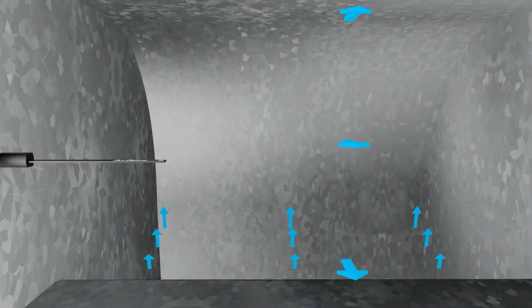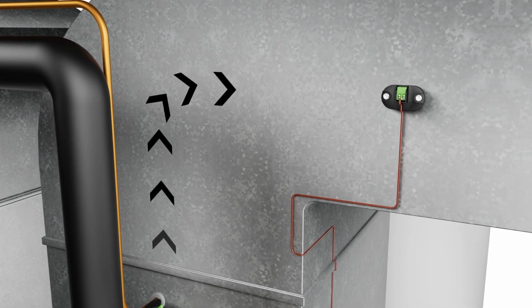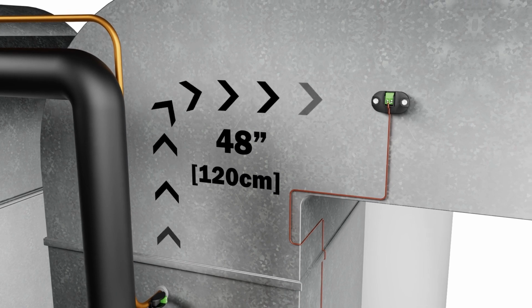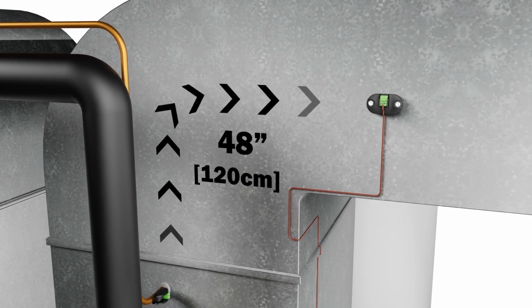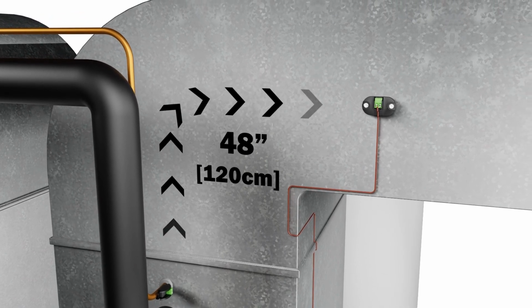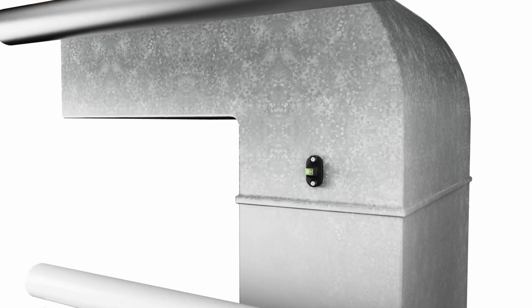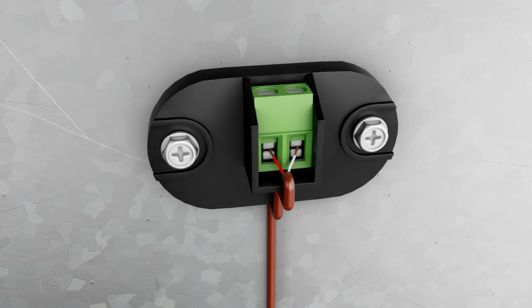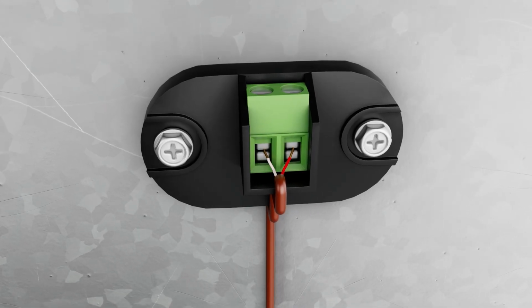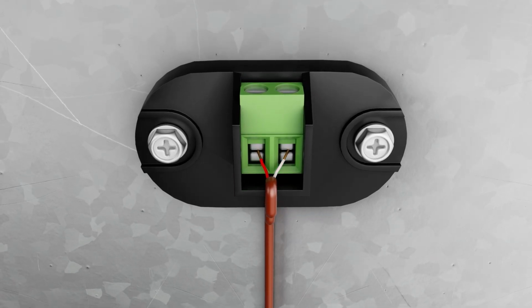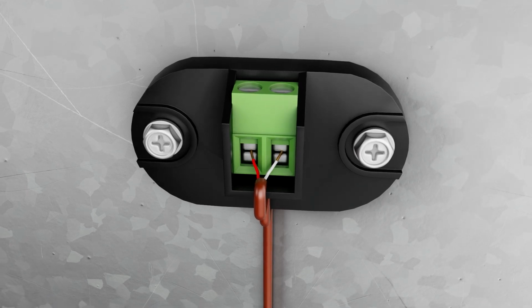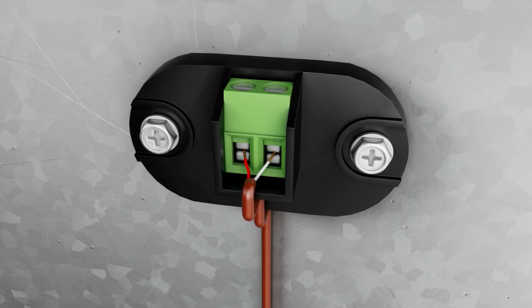airflow in the duct. The supply air sensor should be located at least 48 inches away from the heat exchanger and cooling coil to ensure a thorough mixing of air and accurate measurement. Return air sensor should be located before the filter on the return plenum of the equipment. Wiring is not polarity sensitive. Virtually any gauge will work, but we recommend 2-conductor 18 to 22 gauge.